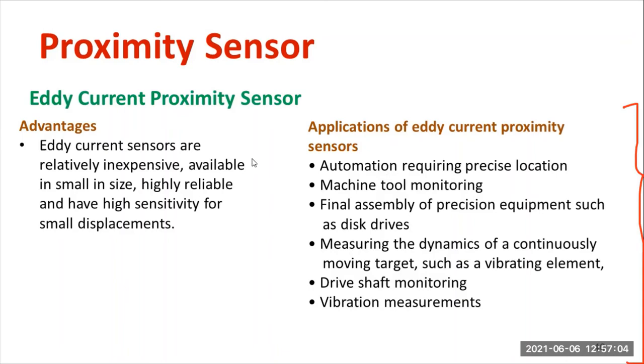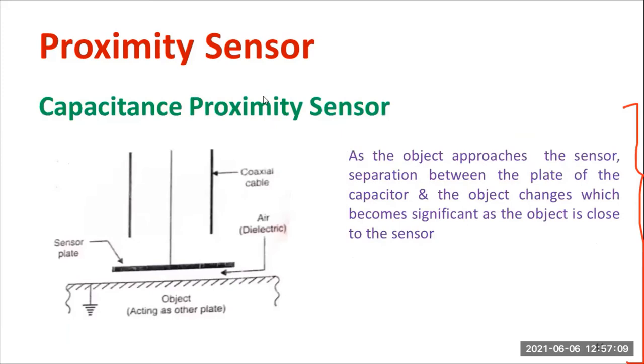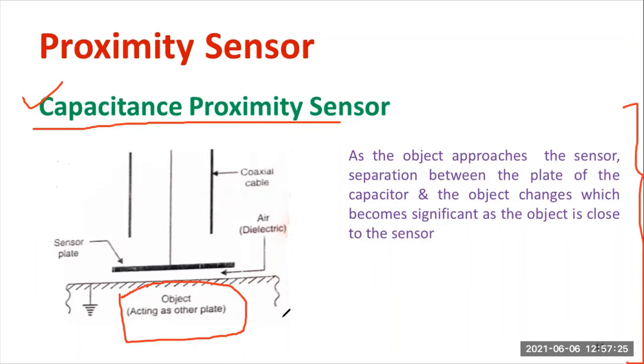Remember that this type of proximity sensor is applicable only for detecting metal objects. To detect non-metal objects such as plastic or rubber, you can use the capacitive type proximity sensor. It has two plates — the first plate is the object itself, directly connected to the first plate; the second plate is known as the sensor plate. In between, you keep a dielectric medium — usually air is considered the dielectric medium. The sensor plate is always fixed.